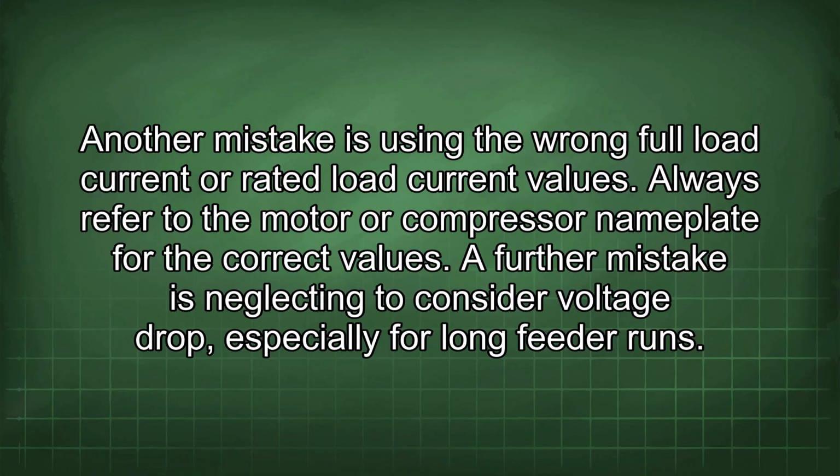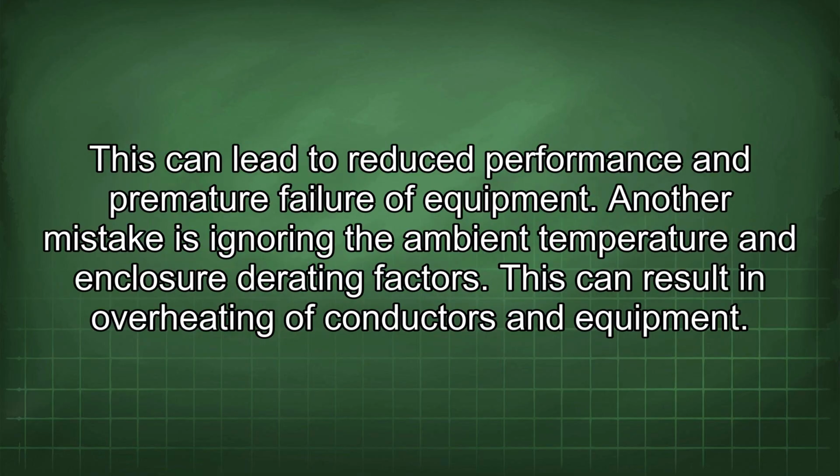A further mistake is neglecting to consider voltage drop, especially for long feeder runs. This can lead to reduced performance and premature failure of equipment. Another mistake is ignoring the ambient temperature and enclosure derating factors. This can result in overheating of conductors and equipment.